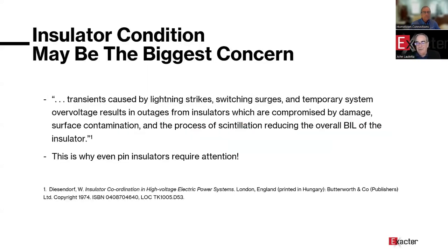This is an interesting report that evaluates how insulators are the biggest concern when it comes to transient flashovers. So a transient flashover is lightning striking your lines, a switching event, a recloser operation. Those operations cause high voltage spikes, transients on the grid, up to 2 times the normal voltage for a switching transient, and even higher for lightning.